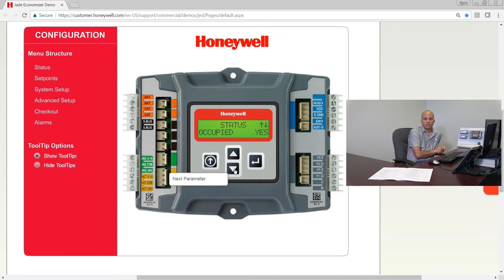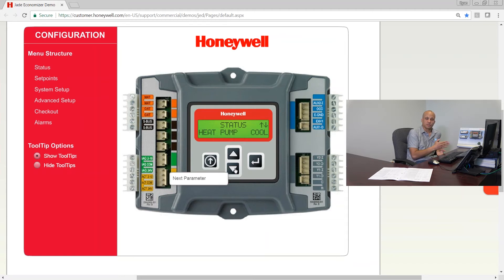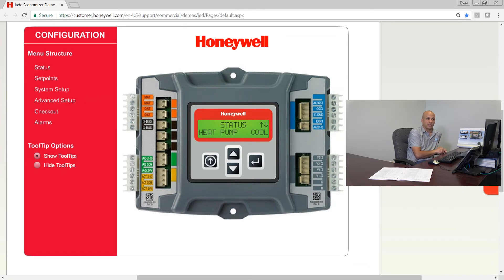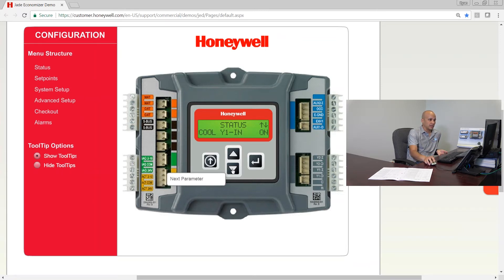Next is 'occupied' — am I in occupied mode? Is my thermostat occupancy output wired to the occupancy input of this economizer controller? It's telling me I'm occupied right now, so that'll say yes. If it's nighttime or any unoccupied mode, it would say no. If you have it physically jumpered instead of wired to your thermostat, it'll always say yes. The difference between occupied and unoccupied is whether I have a minimum ventilation position or not. If I have a heat pump, it'll tell me if I'm in cooling or heating mode at this moment.